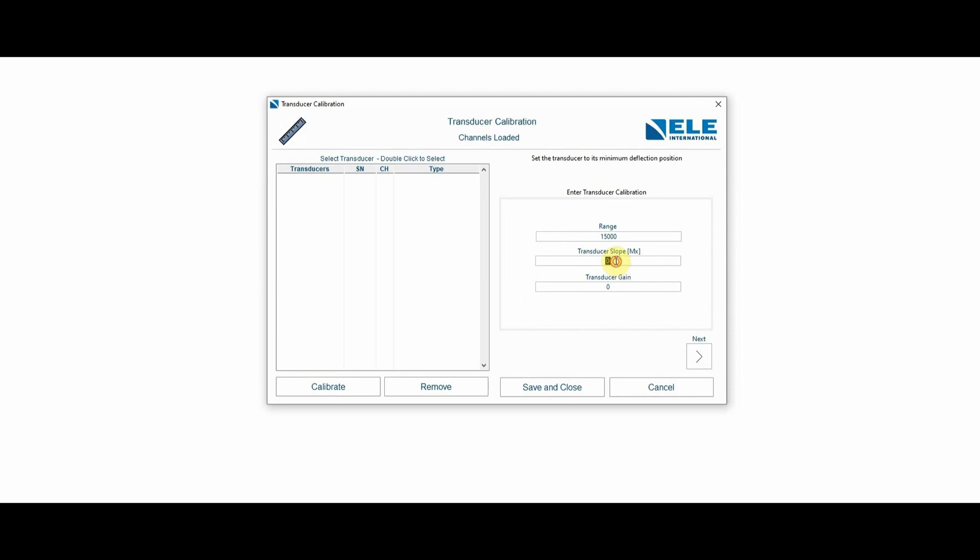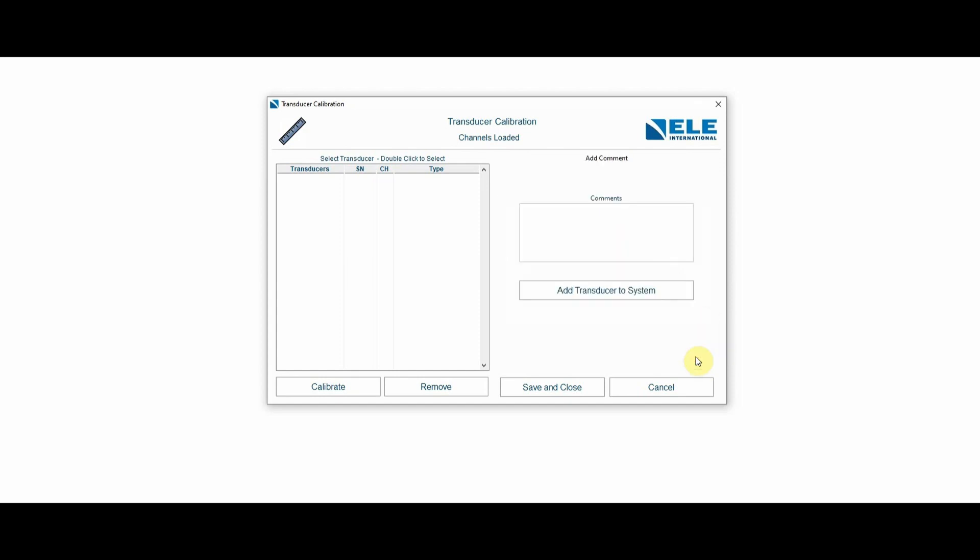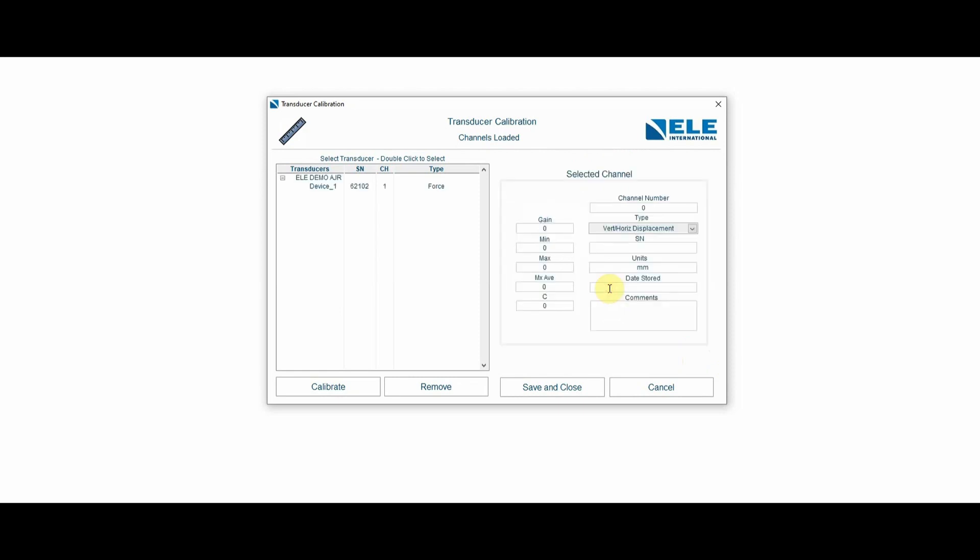It's fairly easy. You're going to enter the transducer slope, which you're going to find in there, and then the gain value, which is also in the transducer calibration certificate. Then I'm simply going to add the transducer to the system.